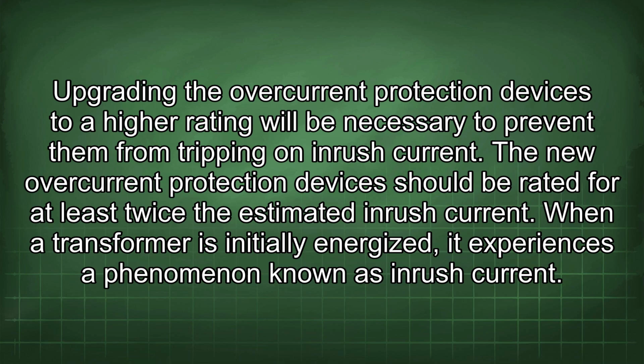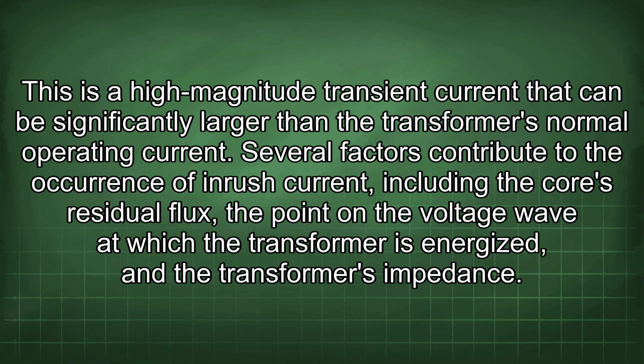When a transformer is initially energized, it experiences a phenomenon known as inrush current. This is a high-magnitude transient current that can be significantly larger than the transformer's normal operating current. Several factors contribute to the occurrence of inrush current, including the core's residual flux, the point on the voltage wave at which the transformer is energized, and the transformer's impedance.